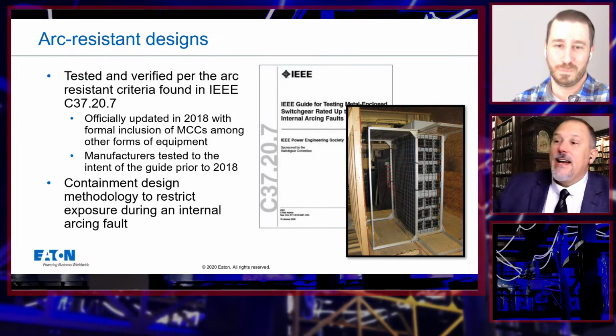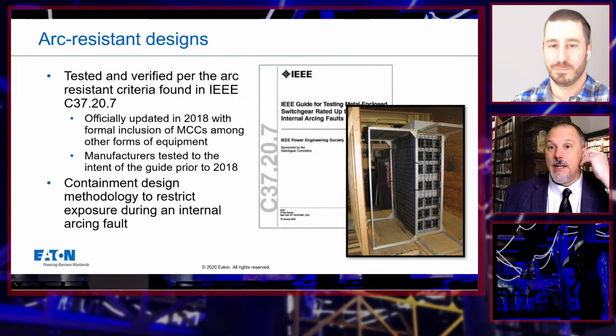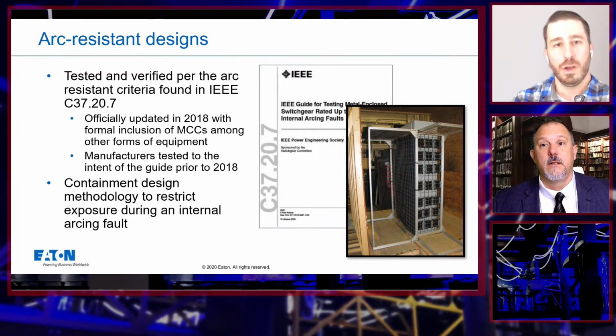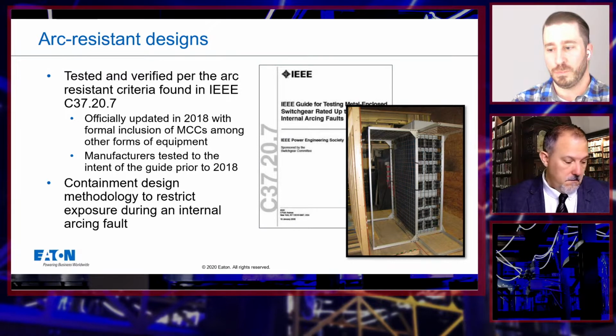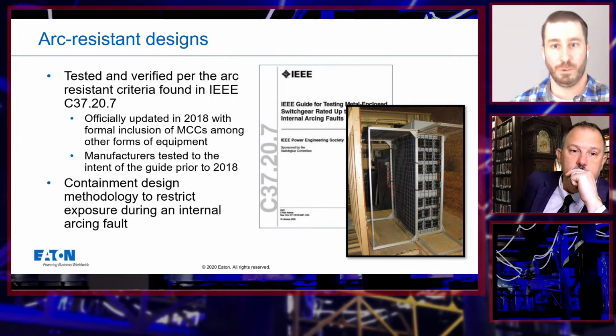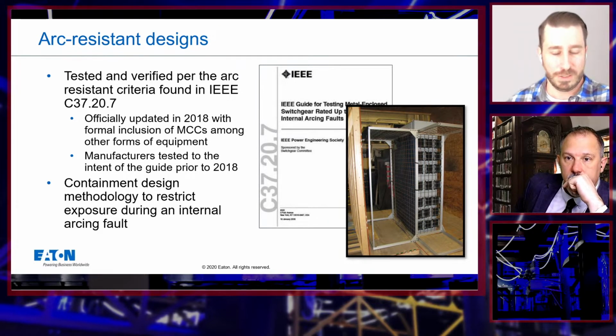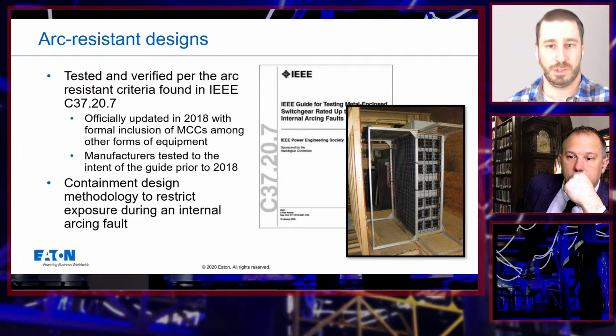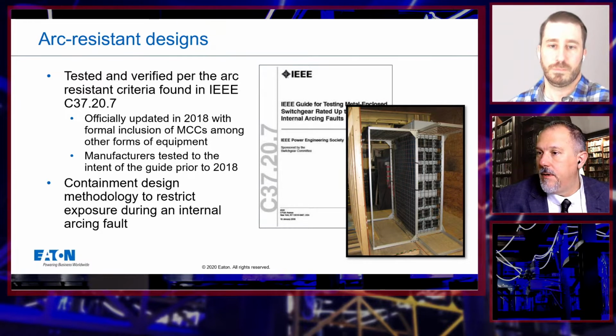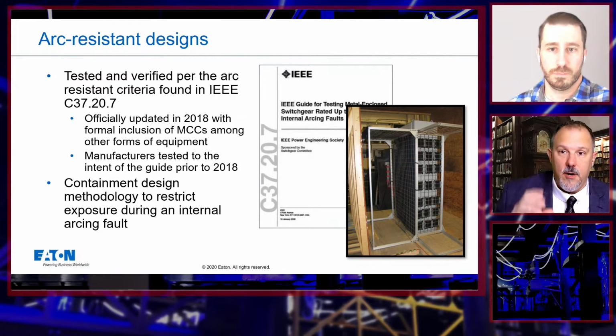Now it's an IEEE standard, but is it UL listed as arc resistant? No, you'll actually work with entities like UL or CSA or whomever as a nationally recognized test lab to assess the equipment. There are considerations around various listings, but in most cases what you'll see is more of a type assessment of various equipment configurations. So you will have a UL label on it, but it'll be listed to this IEEE standard. Correct.